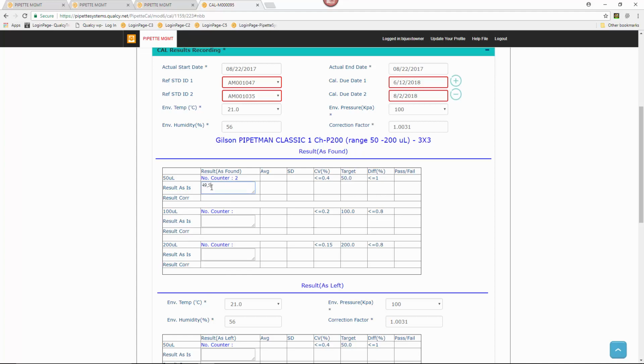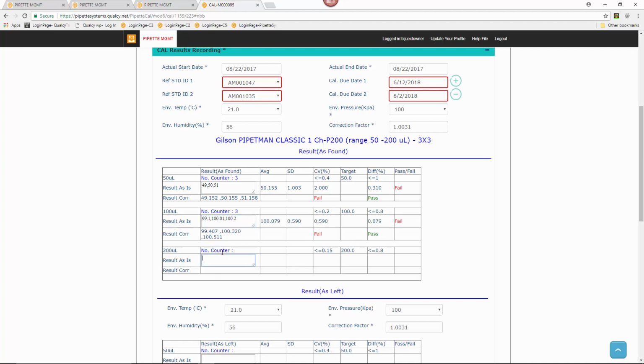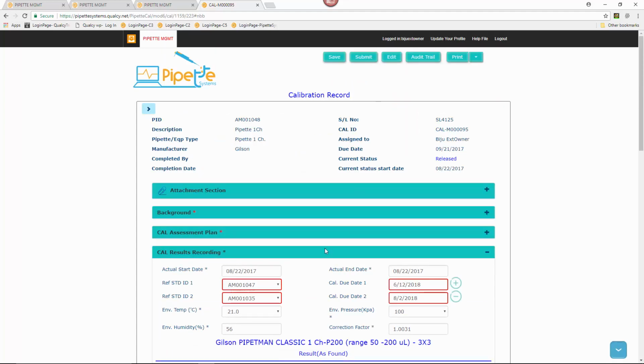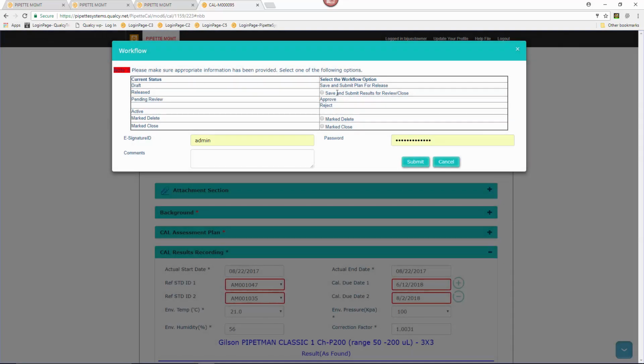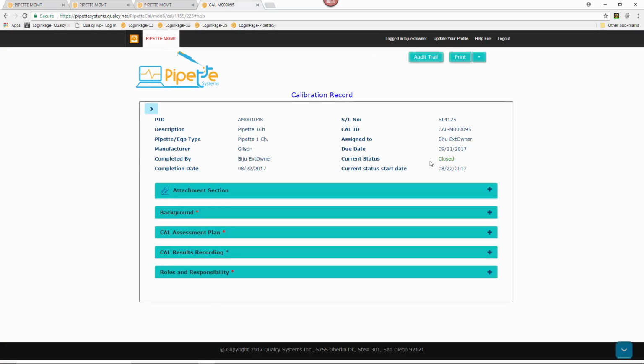So here I'm going to enter some of the calibration data. As you can see, as soon as I enter the data, it does the automatic calculation against the spec, and it shows whether it passed or failed. So now I'll confirm the results that I entered. Click on submit and click on save and submit results for review. Now you see that the calibration data entry is complete and the record has been closed.